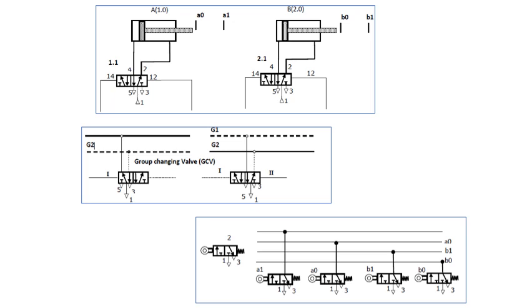Group 1 is indicated by the dotted line — the valves in group 1 will get supply from group 1. One additional memory valve is used to switch over the signals from group 1 to group 2. Normally we have four limit switches — two for each cylinder — and two pilot-operated double-acting 5/2 valves, one for each cylinder. In addition, there is one more pilot-operated valve used to switch over the signal from one group to the other group.